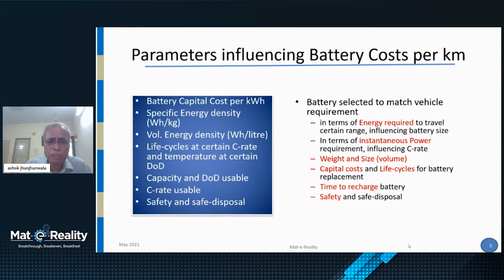A very important parameter is life cycles of a battery, because a battery does not last forever. Its life keeps deteriorating as it is used, and depending on the kind of battery, either 500 to 700 cycles, 1500 cycles, or 3000 cycles, the battery becomes pretty much useless and has to be replaced. The life cycles depend not just on charging and discharging rate, but also on the temperature of operation. For example, in India you operate at 45 degrees centigrade, and that will always be a problem.